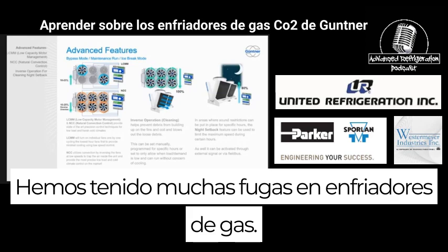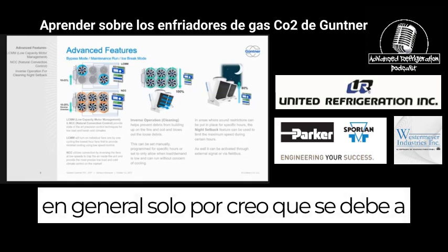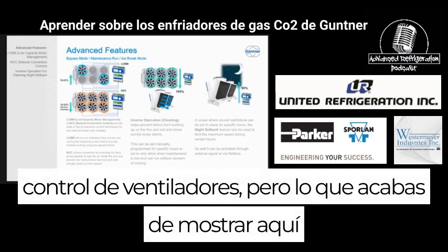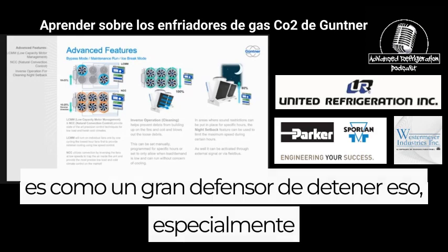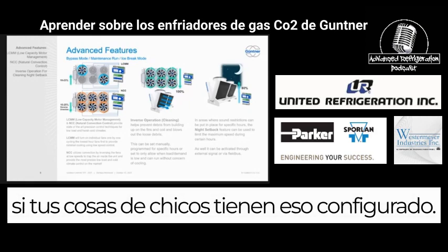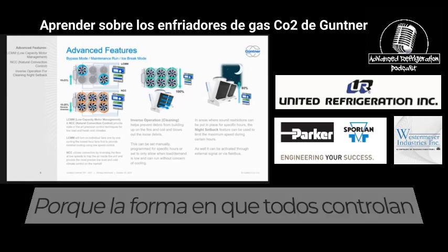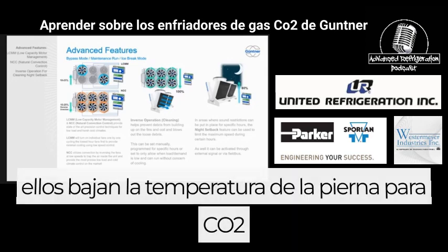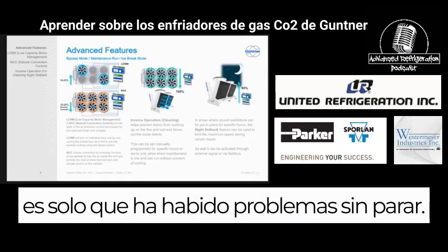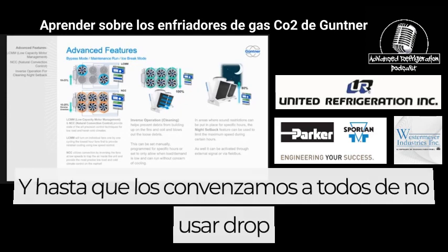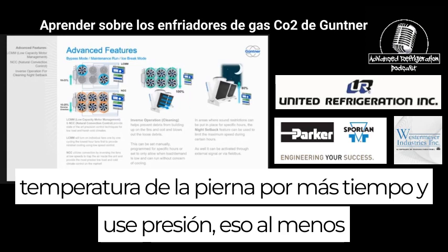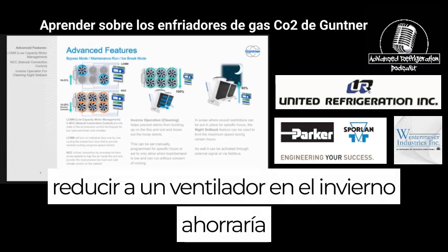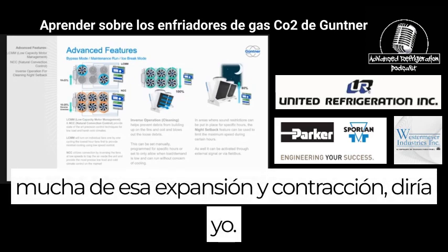We've had a lot of leaks on gas coolers in general, I think due to fan control. But what you just showed is a big proponent of stopping that, especially if your stuff has that set up, because the way that they're all controlling them off drop leg temp for CO2 has been nonstop problems. And until we convince them all to not use drop leg temp any longer and use pressure, at least dropping down to one fan in the wintertime would save a lot of that expansion and contraction, I would think.